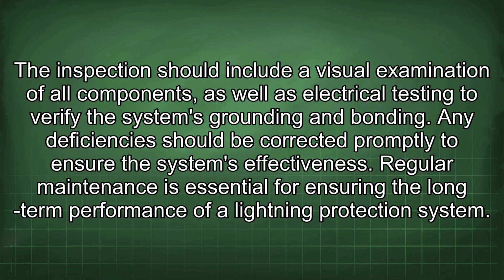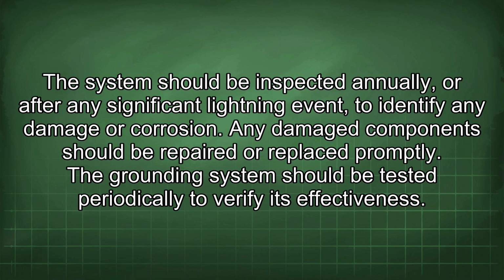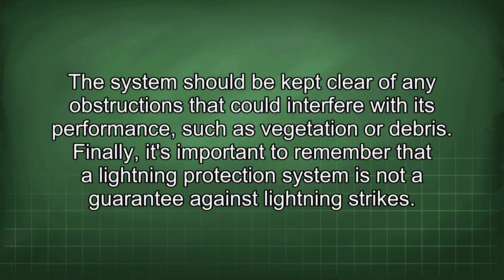The inspection should include a visual examination of all components, as well as electrical testing to verify the system's grounding and bonding. Any deficiencies should be corrected promptly to ensure the system's effectiveness. Regular maintenance is essential for ensuring the long-term performance of a lightning protection system. The system should be inspected annually or after any significant lightning event to identify any damage or corrosion. Any damaged components should be repaired or replaced promptly. The grounding system should be tested periodically to verify its effectiveness. The system should be kept clear of any obstructions that could interfere with its performance, such as vegetation or debris.